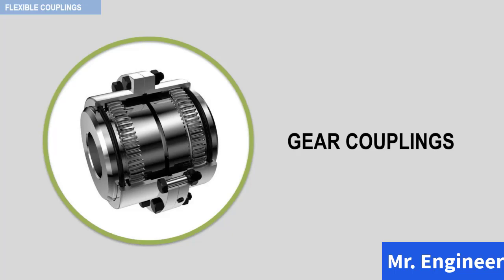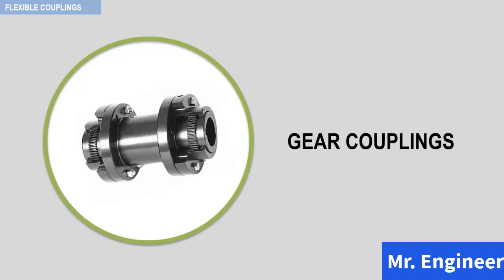The following figure depicts a typical example of a gear type coupling. Gear couplings usually include two separate gear mesh units as highlighted here. Each gear mesh unit consists of an external gear which fits closely into an internal gear. The internal gear can either be part of the coupling hub assembly, as seen here, or mounted on each end of the coupling spacer assembly, as seen in the second example.